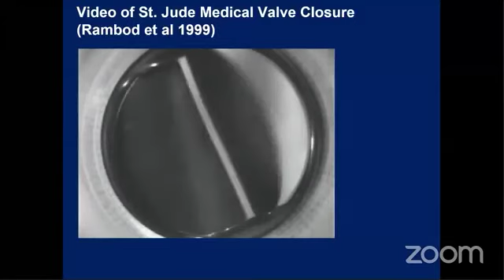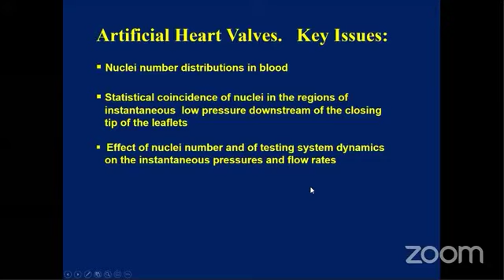All right, so what are some of the problems? To understand this, there are several things you need to follow. First of all, what are the nuclei number distributions in blood? As far as I know, no one has measured them. And in order to quantify cavitation in any context, you need to know the nuclei number distributions. Secondly, this cavitation depends upon the coincidence of nuclei in the regions of instantaneous low pressure. And that's hard to model and hard to completely quantify. Moreover, thirdly, both the nuclei number and the testing system are usually different from those in the body. And so you have to factor in the different system dynamics in understanding the flow and the tests in the laboratory.